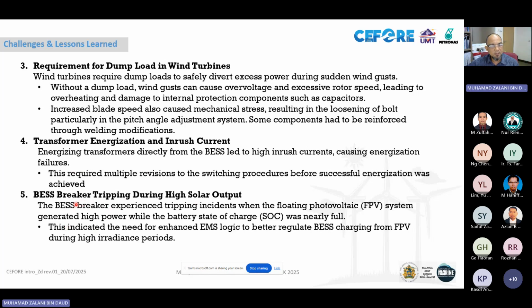Number 5 is battery energy storage system breaker tripping during high solar output. This happens when state of charge is nearly full, like during sunny days. Our FPV, floating photovoltaic system, can generate up to 220 kilowatts, and up to 170 kilowatts for charging the battery energy storage, which is quite high power. So when the battery energy storage state of charge is nearly 100%, it triggers the circuit breaker to trip because of the high amount of charging power.